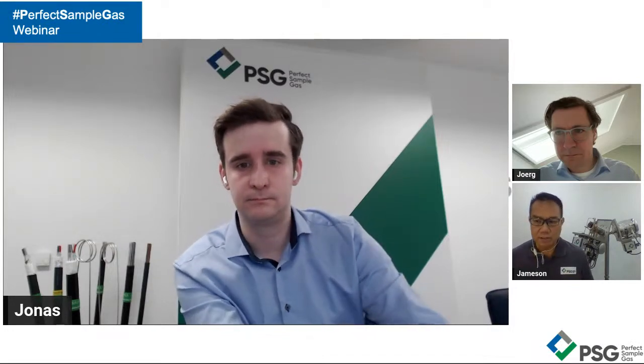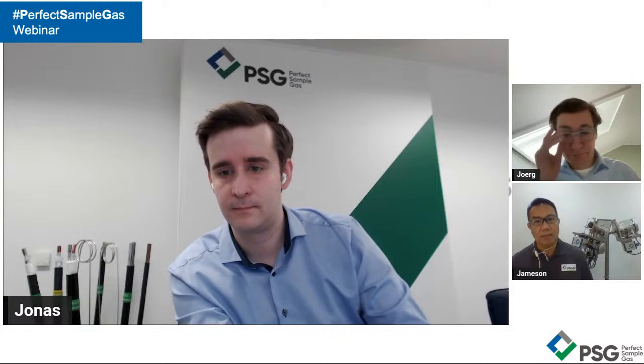is what percentage of moisture can be removed by the PSG cooler. Jameson, what would you say? What would we recommend there? Yeah, so let me explain. In the cooler itself, there are a couple of things that we have to consider. Firstly, the heated sample itself, before it enters into the cooler, must be above water and acid dew point. That is a critical number one. Number two, at the point of entry, the sample must again be above water and acid dew point. This is so important so that you do not have a long unheated naked tubing going into the gas cooler. Number three, you have to ensure that the sample pump is not higher than our specification. All right, it is not higher than.